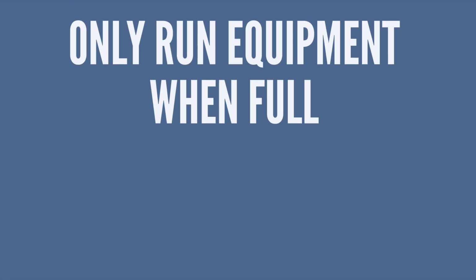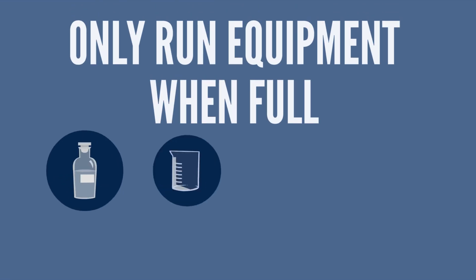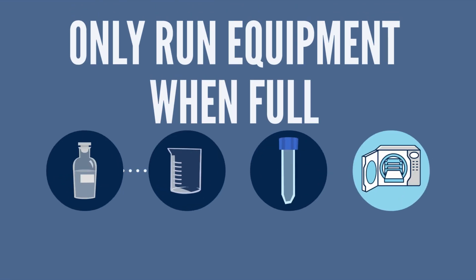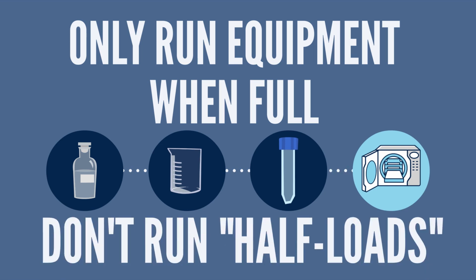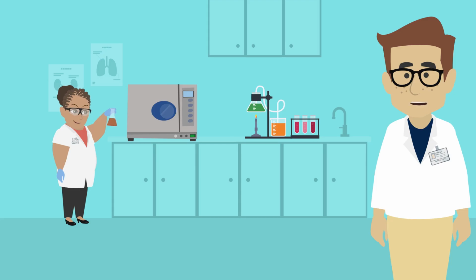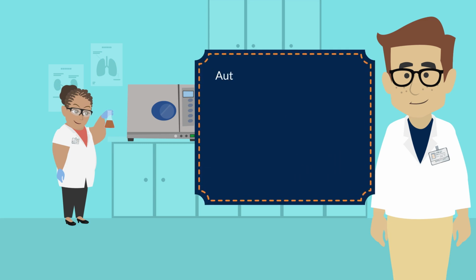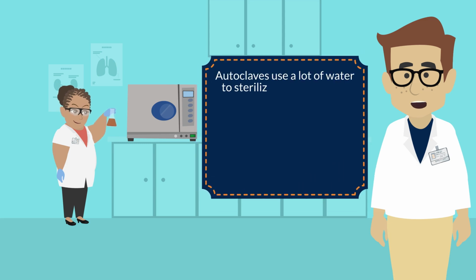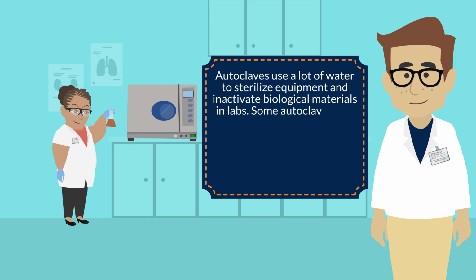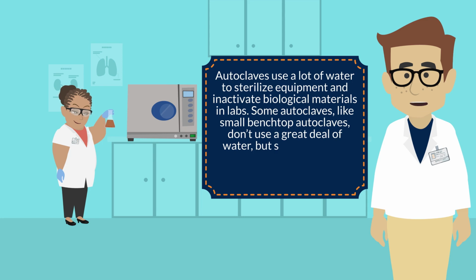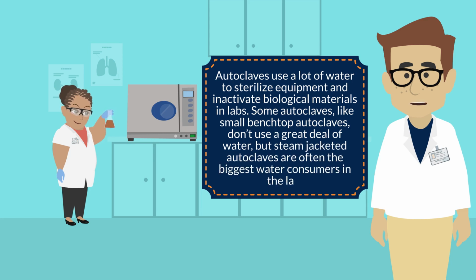Also, only run equipment that uses water, like glassware washers and autoclaves, when they're full. No half loads allowed. The biggest water waster? An autoclave. Autoclaves use a lot of water to sterilize equipment and inactivate biological materials in a lab. Some autoclaves, like small benchtop autoclaves, don't use a great deal of water, but steam-jacketed autoclaves are often the biggest water consumers in a lab.